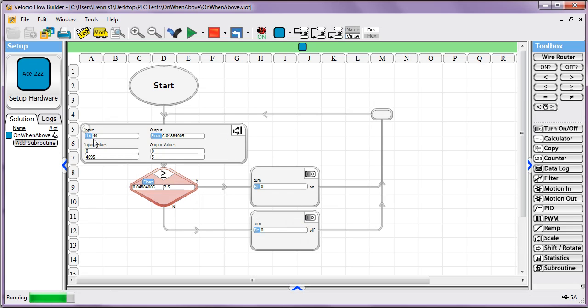Okay, so you can see my input values coming in, and it should go basically from 0 to 5. It's the scaled value. And when it's over, you see it goes to green, and when it's under, this thing turns red, and we can actually see, because I've hit this name value button, the value inside that bit turn on and off based on me adjusting my input voltage, and on my simulator and my PLC, I can see the output light turning on and off.